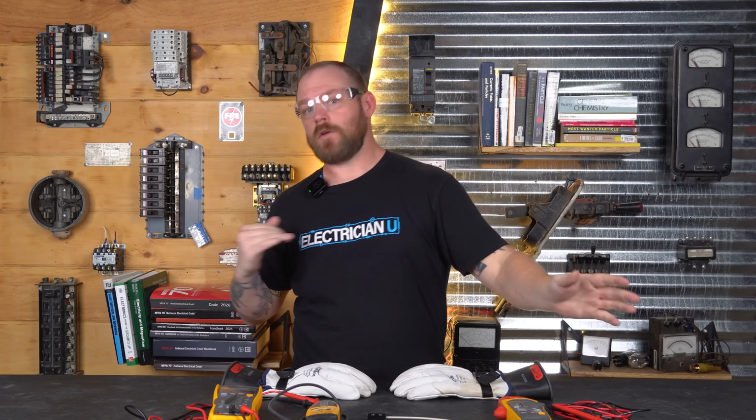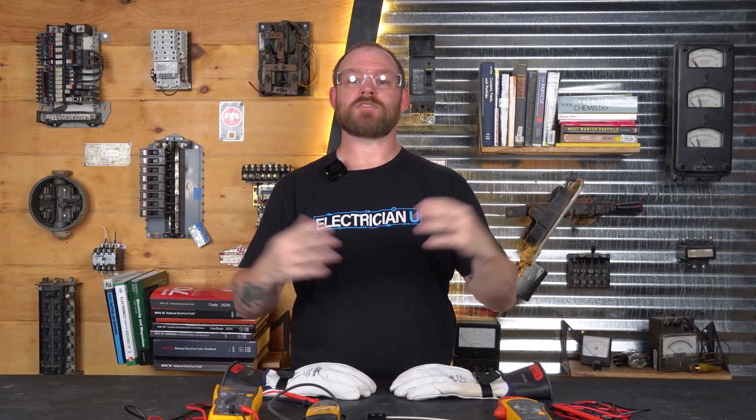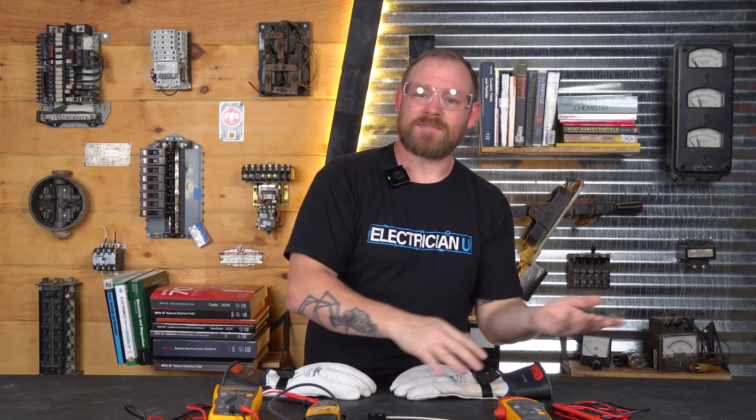There's a difference when you have voltage actually being dropped because a load's turning on, or you've got distance or something like that that's causing voltage that you would expect to be 120 to drop to 87 or something like that. A lot of times when you kick a heavy load on, voltage will drop just until the inrush of a motor calms down and the voltage will come back up. So there's a voltage drop at the beginning of things.